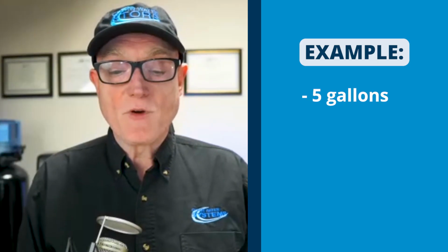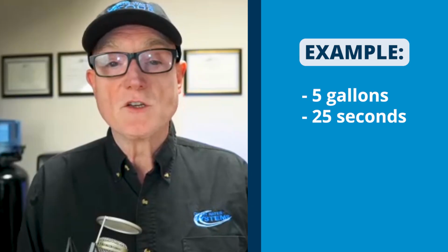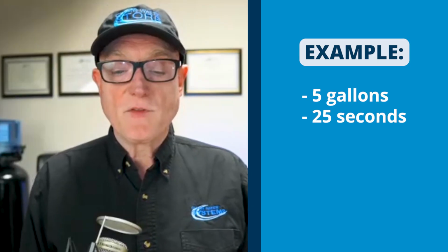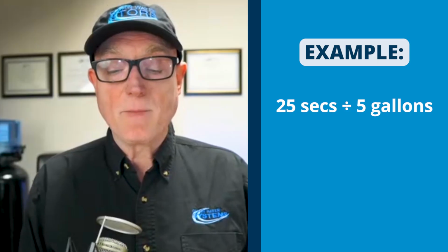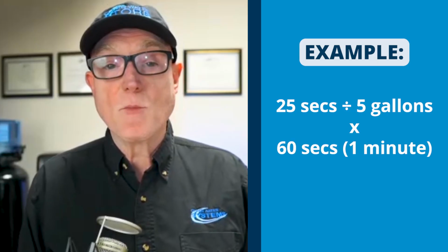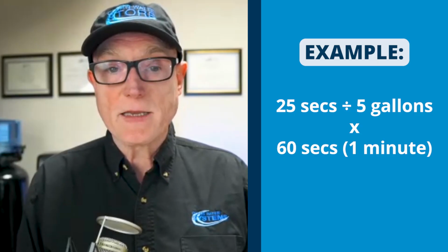Some people have very small pressure tanks. And then the number of seconds in the pump cycle to refill the pressure tank was 25 seconds. So the gallons per minute is you take 5 gallons divided by 25 seconds, and then you multiply it by 60 seconds in a minute, and that gives you gallons per minute. So in this case, he had 12 gallons per minute.